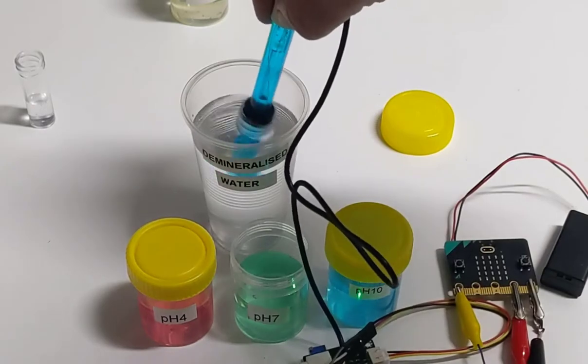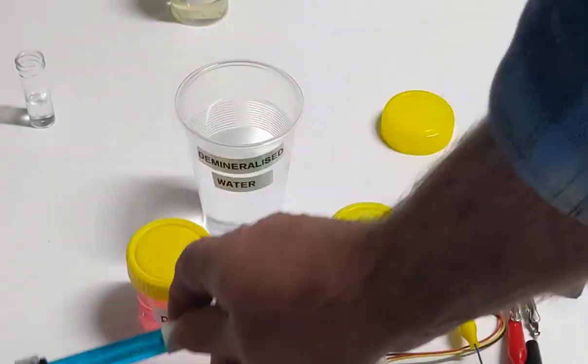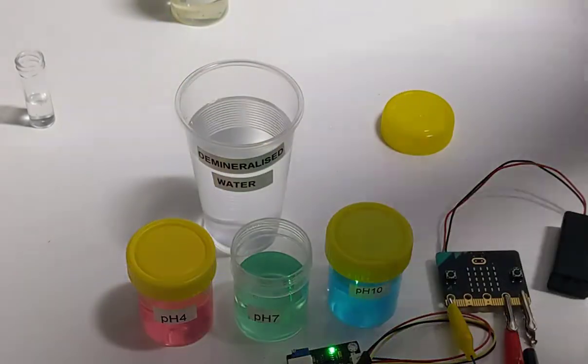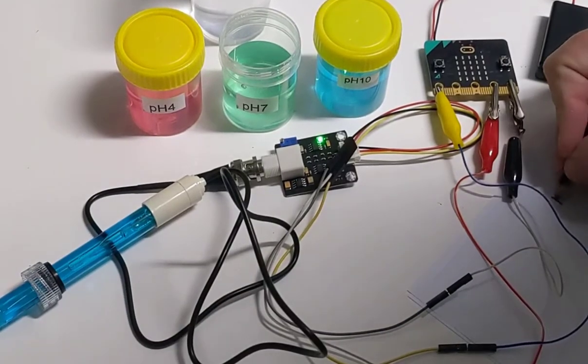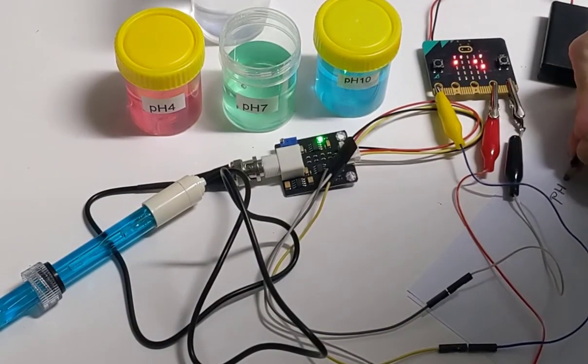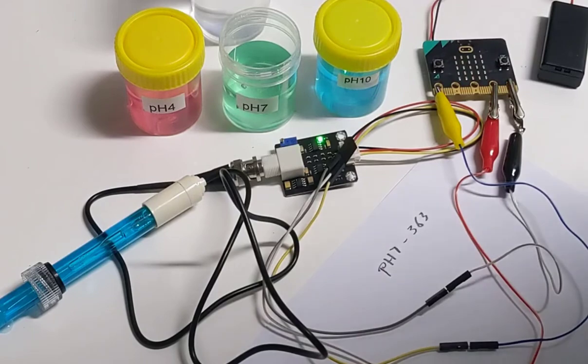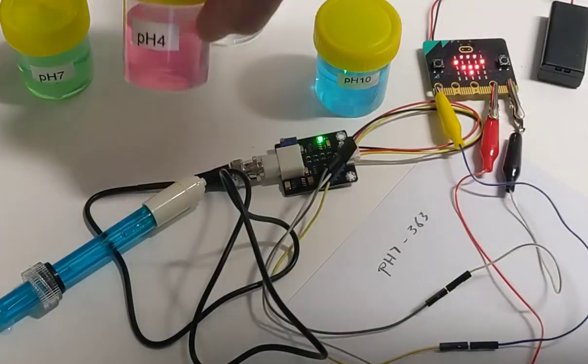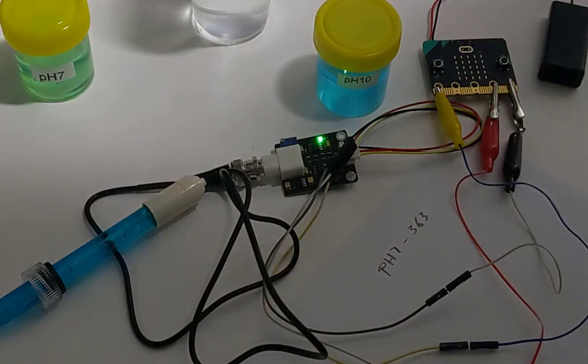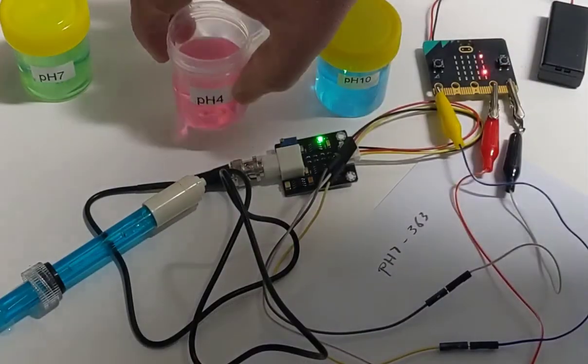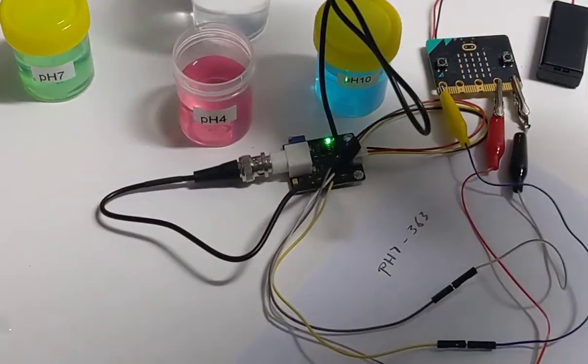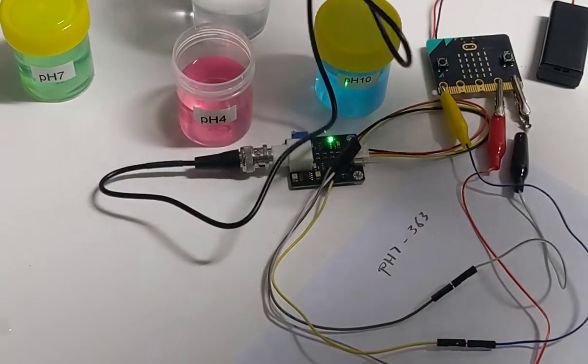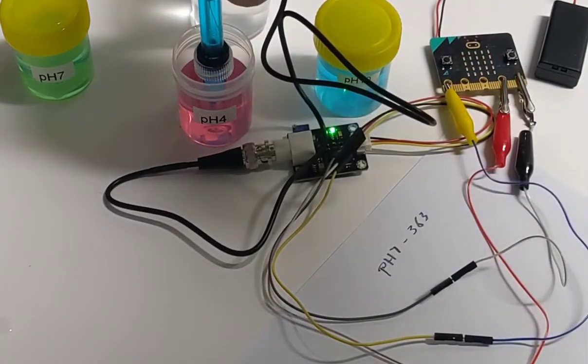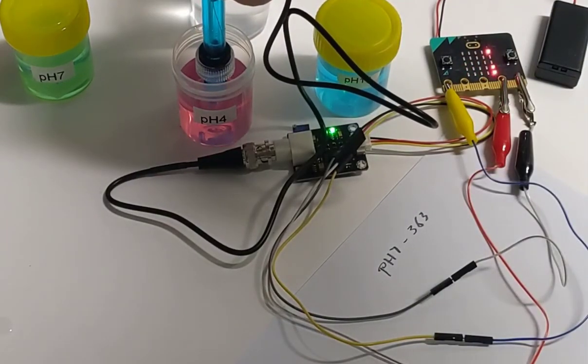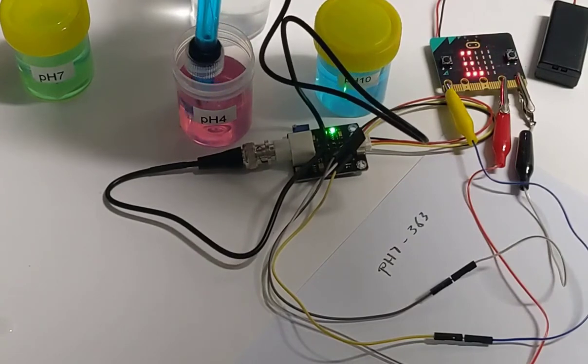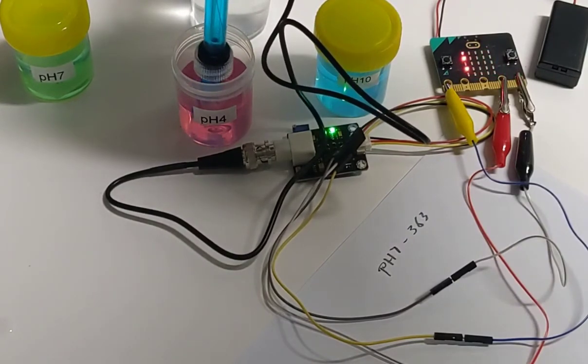I'll just wash the sensor out, and very quickly I will write down that pH 7 gave a value of 3.63. Now we'll try pH 4. This is somewhat acidic. I've already washed it in demineralized water. Place the sensor into the pH 4 and shake it around just a little bit, and I'm getting 2.23.